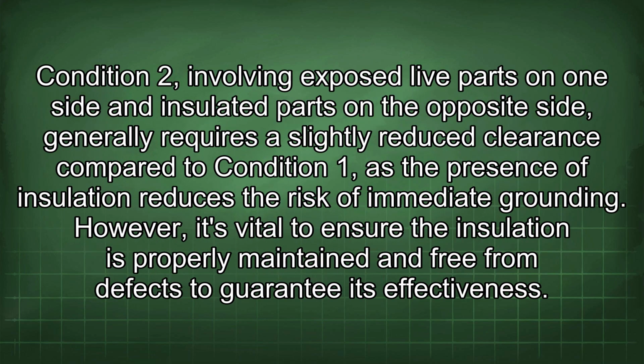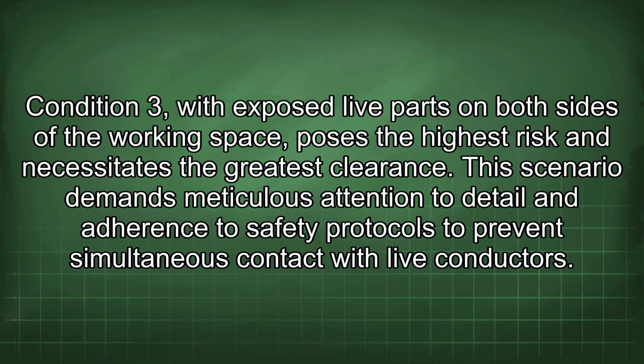Condition 2, involving exposed live parts on one side and insulated parts on the opposite side, generally requires a slightly reduced clearance compared to Condition 1, as the presence of insulation reduces the risk of immediate grounding. However, it's vital to ensure the insulation is properly maintained and free from defects to guarantee its effectiveness.